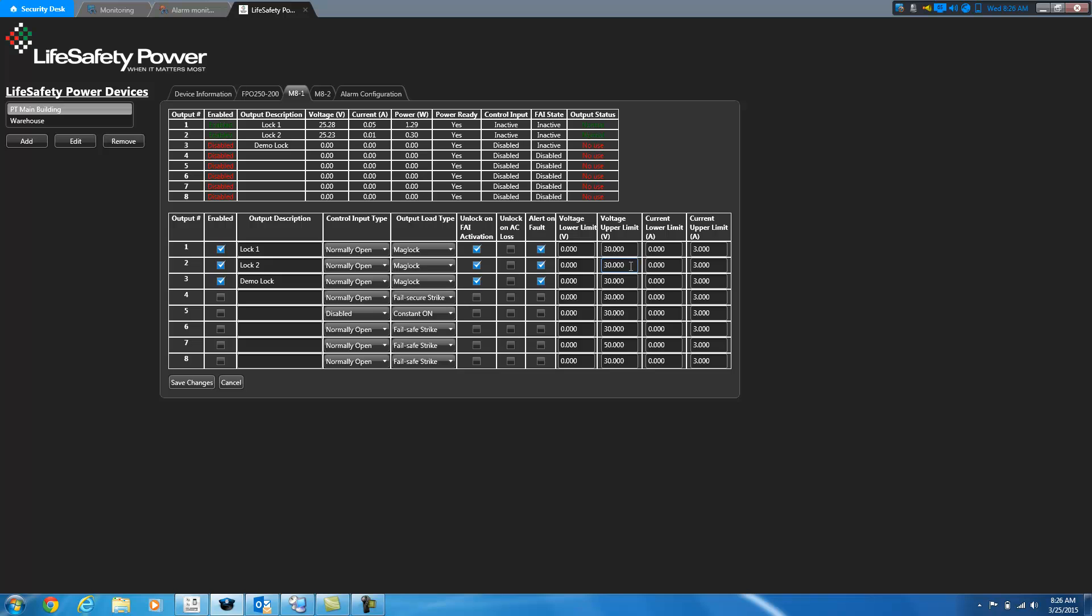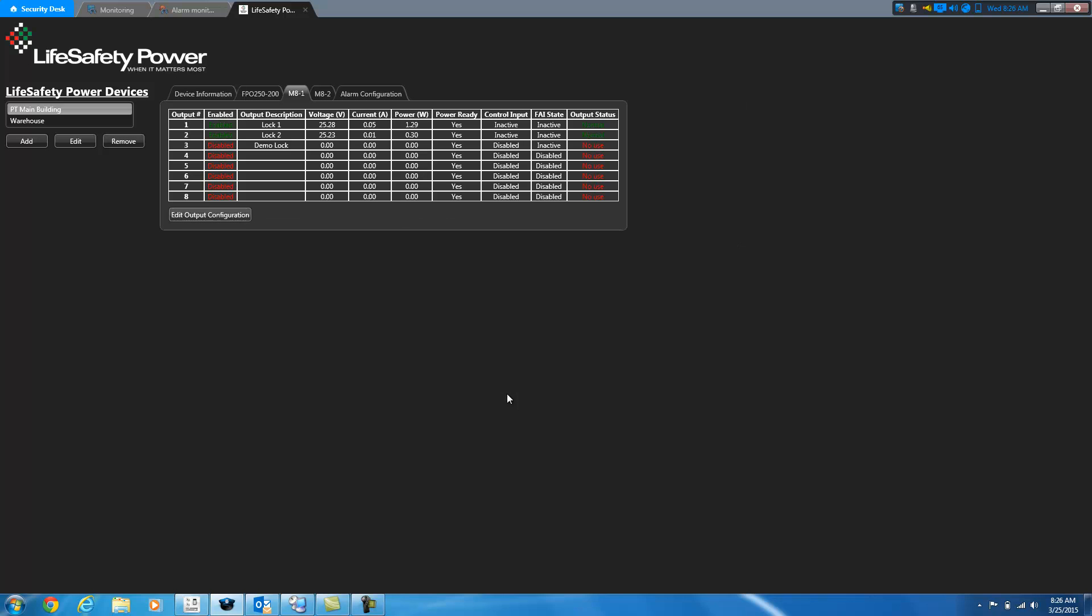And then you can set the upper and lower voltage limits. I'm going to go ahead and set the voltage limit on this one at 24 volts, because we're currently pulling 25, so that you can see what the alert looks like when it comes through. And then I'm going to save my change, and it's going to send the information to the board, and then it will refresh, and we should see it change here in a minute to show us that we have a fault status on number two, and that number three is now enabled, and then it'll start telling us how much voltage it's pulling, and what its current status is. So you can see here it's a fault status.